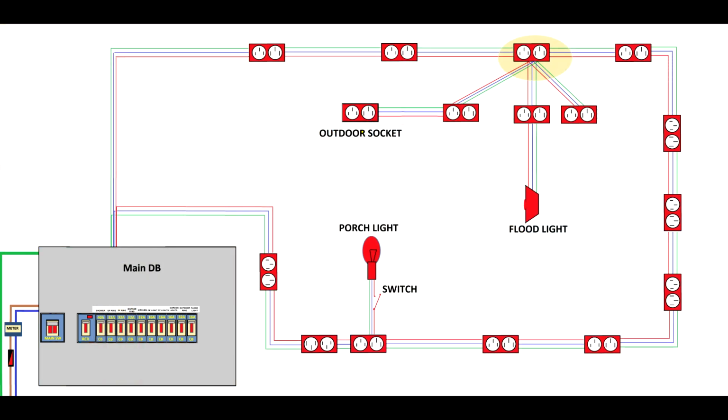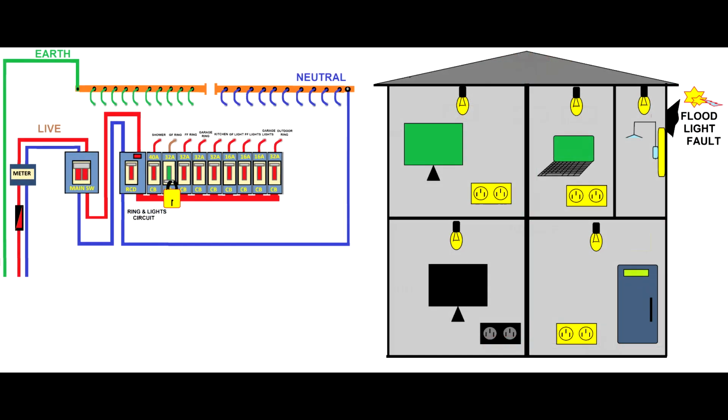I didn't fix it. I just eliminated that section which was faulty, and I explained to the customer he's got an incorrect circuit and he can catch fire. This type of circuit is not something that you want to have at home. That's a fire danger. You protect a 2.5 cable with 32 amps, and if it's not a ring circuit and it is an unprotected spur, then you might end up in trouble.